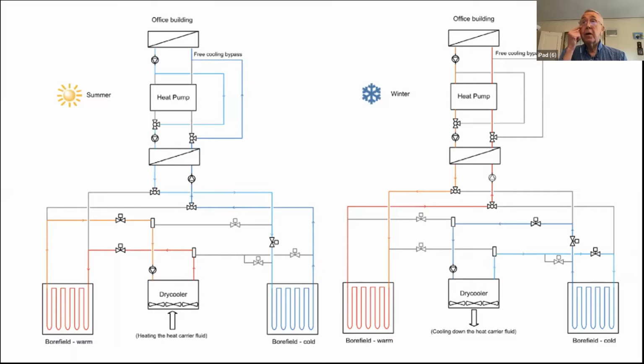So on the right-hand side of this example is the opposite season. It's now the coldest night of the winter. So the dry cooler is feeding nice cold water into the right-hand bore field to make it as cold as possible. And at the same time, you've got nice warm water from the left-hand bore field feeding up. In this case, it's using the heat pump. And the heat pump has a compressor which takes some electricity. So the electricity into the heat pump and the warm water together provide the heat for the building.